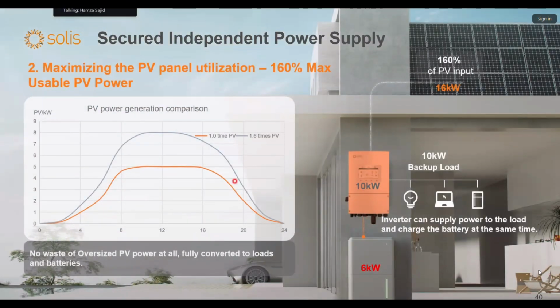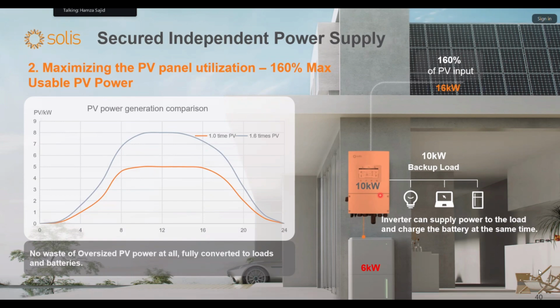Maximum PV utilization. A 10 kilowatt inverter can have 16 kilowatt usable PV power. In this case, 6 kilowatt from the PV can be used to charge the battery at the same time, and 10 kilowatt can be used to support the load. So Solis has an edge on other brands, in that it can utilize up to 160% of the installed PV. So there is no waste of oversized PV.